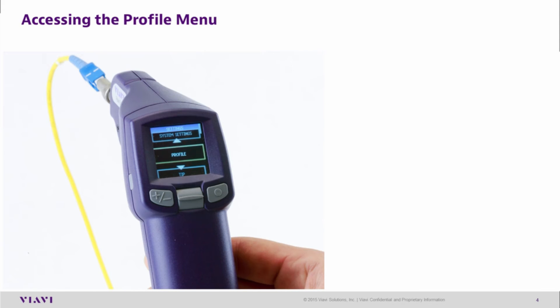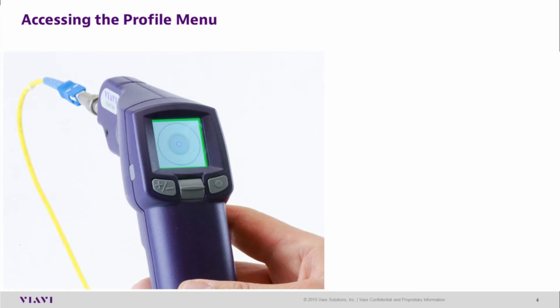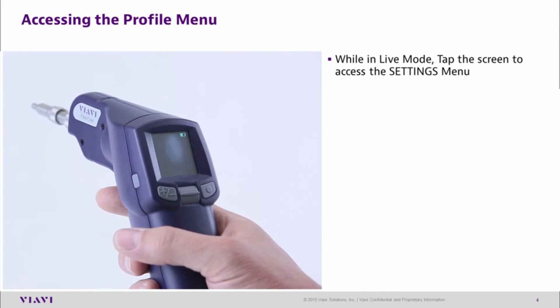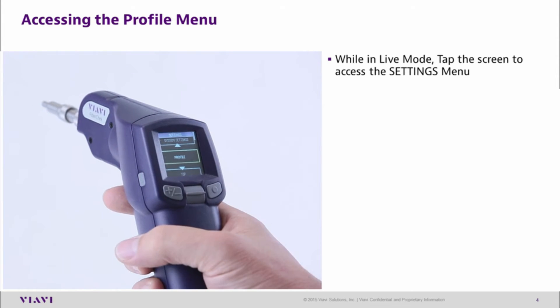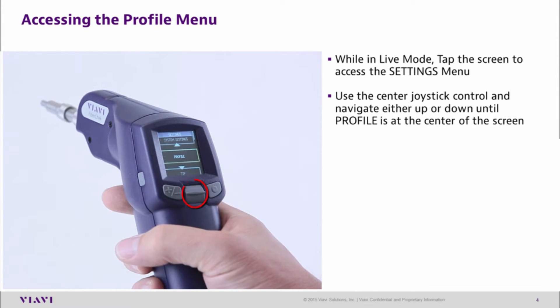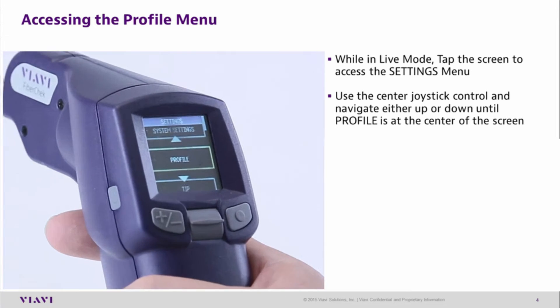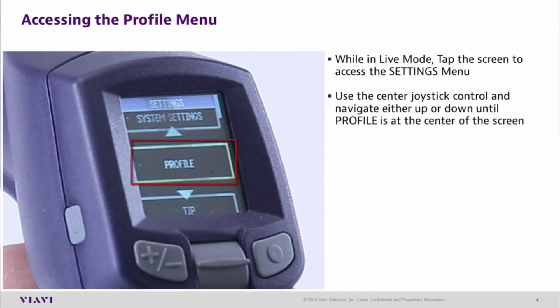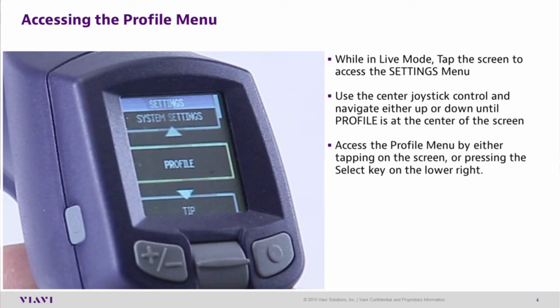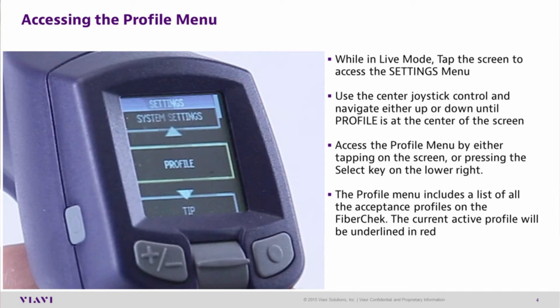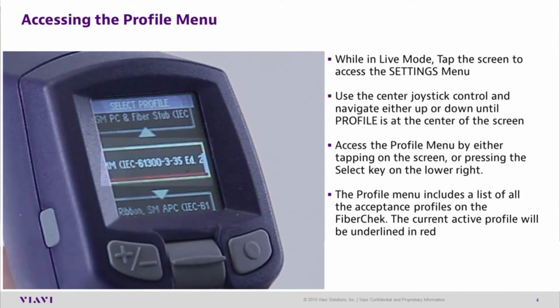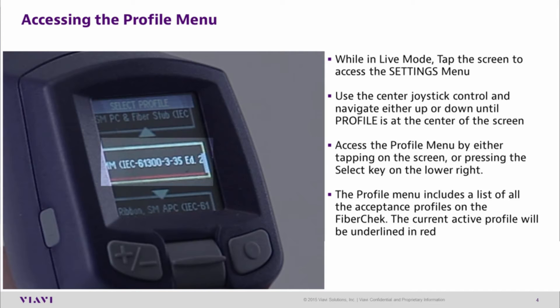Accessing the profile menu. Profiles are criteria used to evaluate connectors being tested. While in live screen mode, tap the screen to access the settings menu. Use the center joystick to navigate up or down until profile is at the center of the screen. Access the profile menu by either tapping the screen or pressing the select key in the lower right. The profile menu indicates a list of all acceptance profiles on the FiberChek Pro. The current active profile will be underlined in red.